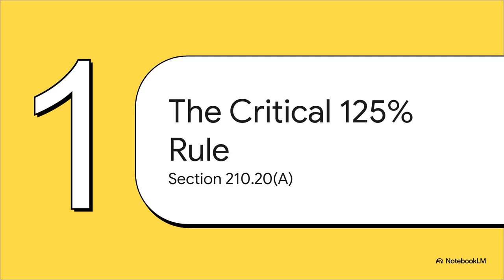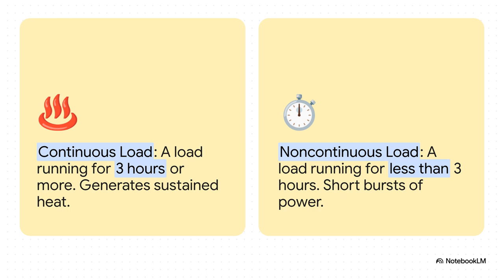People often call it the 125% rule, and honestly, it's a brilliant piece of safety engineering. Now, to really get this rule, we first have to understand that the code sees two completely different kinds of electrical loads. First, you've got a continuous load. That's anything that's running for 3 hours or more. Think office lighting or water heater. Then you have a non-continuous load, which runs in short bursts, like your vacuum cleaner.